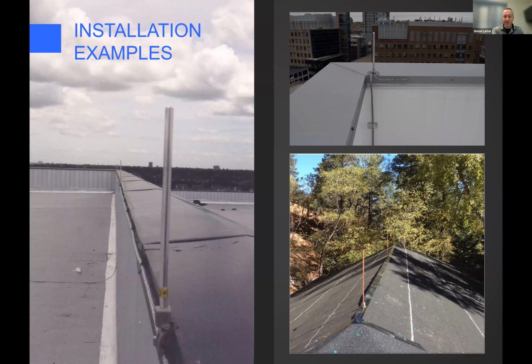Those are 300 millimeter tall aluminum lightning rods. Like I said before, aluminum is the best material to use in contact with galvanized steel or painted steel parapet copings. You can see there, those are side-mounted bases on the side of the aluminum on the left. On the top right there, you've got an adhesive base that's glued to the top. That's probably to get it within 600 millimeters of that outside corner there. And then the lightning conductor goes down from there.